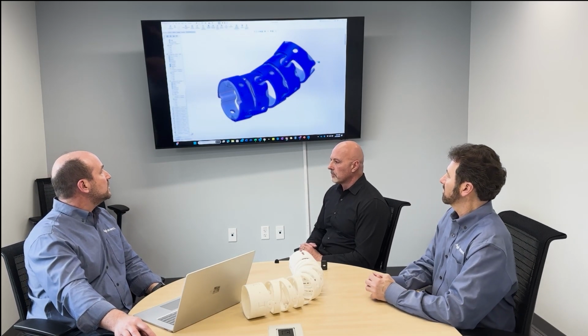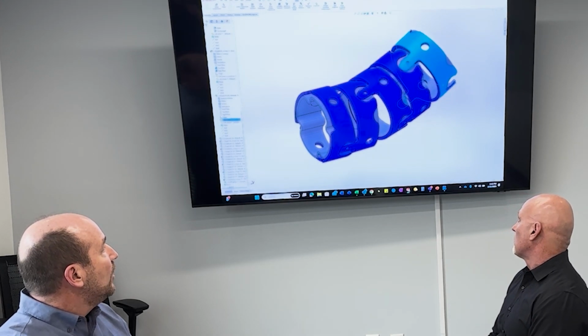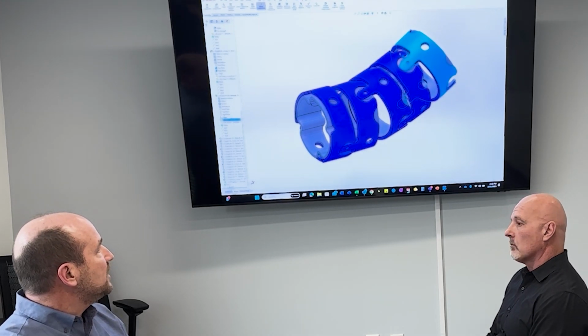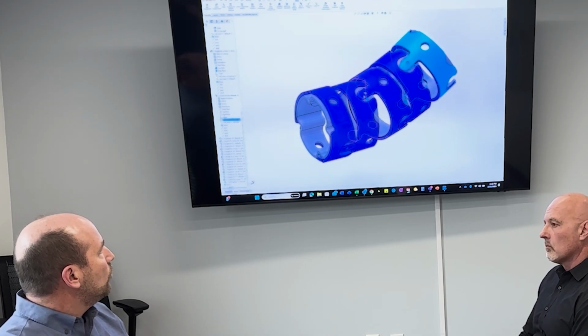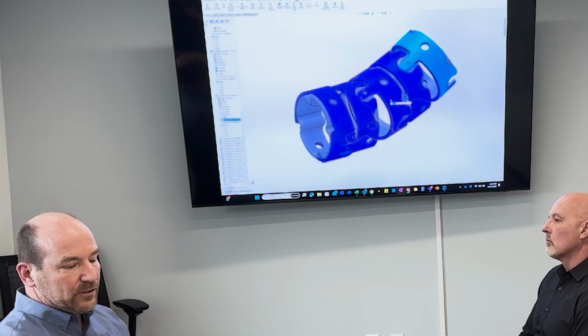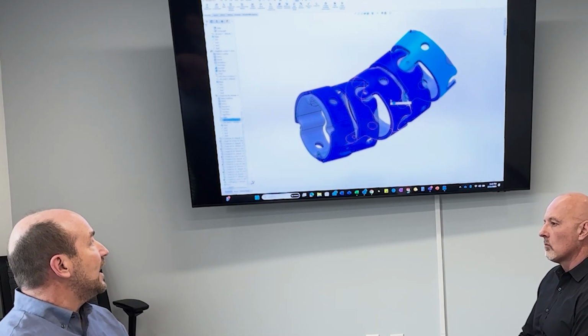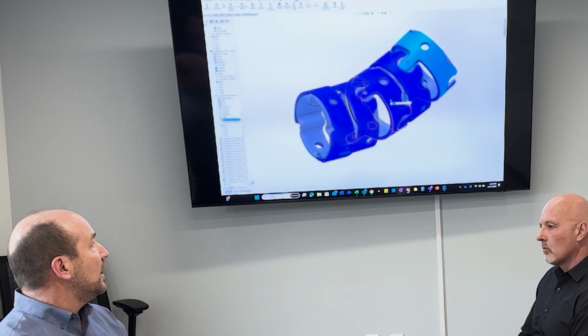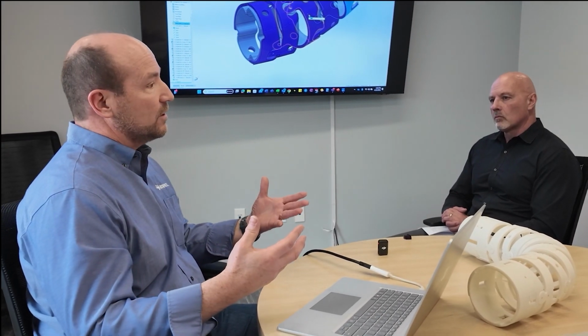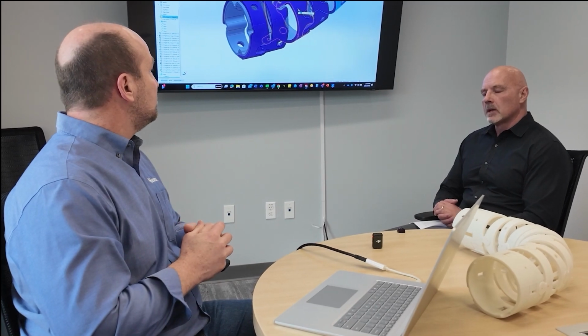And so we came up with this design, inner two tubes, a tube within a tube, and you can see how it will move within it. You've got a puzzle piece up here. It's captured within two tubes, and we laser weld here. So we use our laser welding ability as well as our laser cutting. So this is a hypotube within a hypotube, two sizes that fit within a tight tolerance that we can then manufacture and produce at a pretty inexpensive cost.